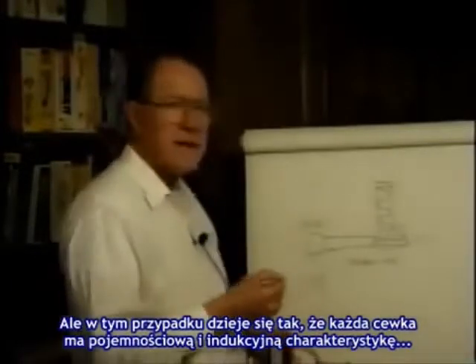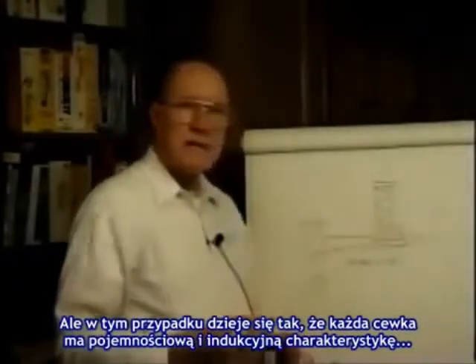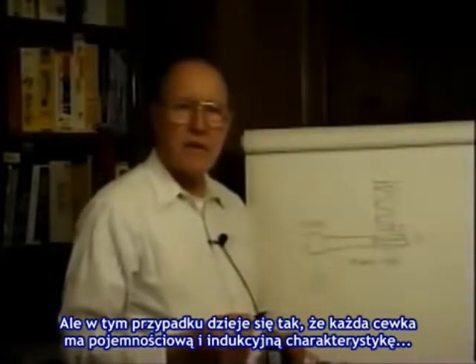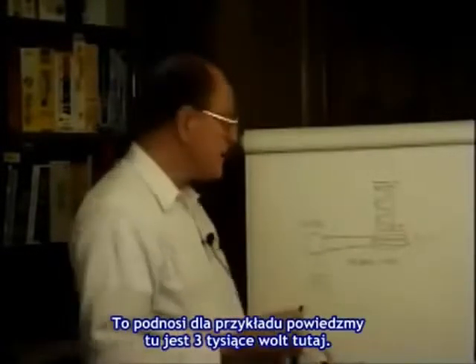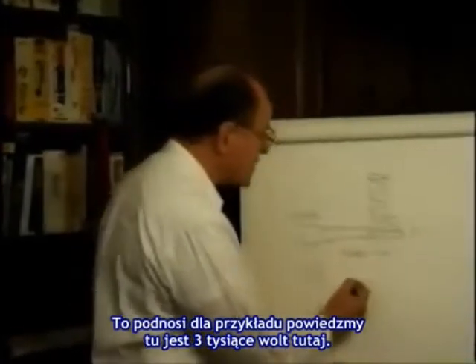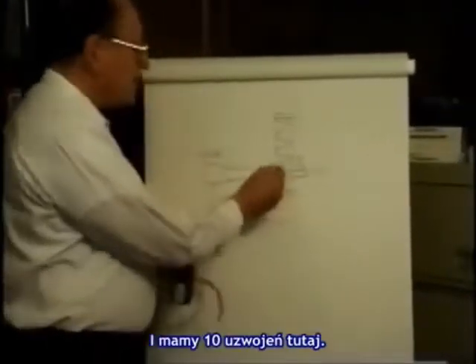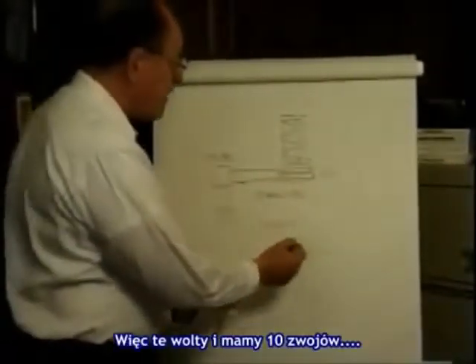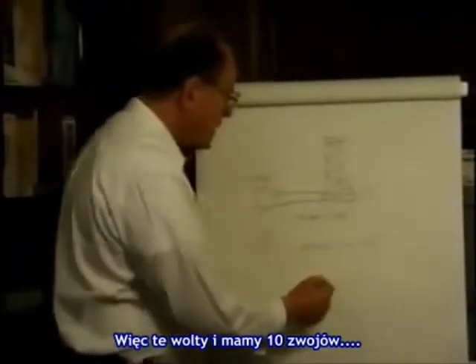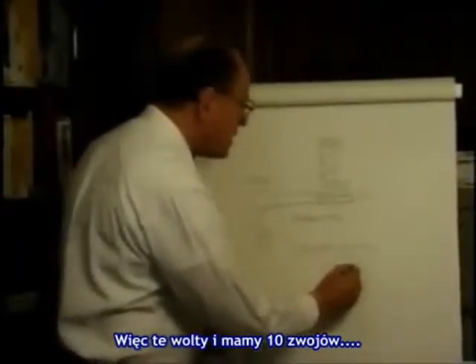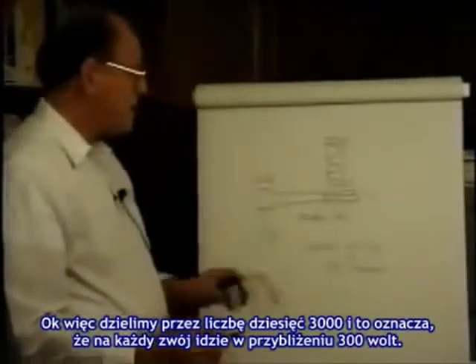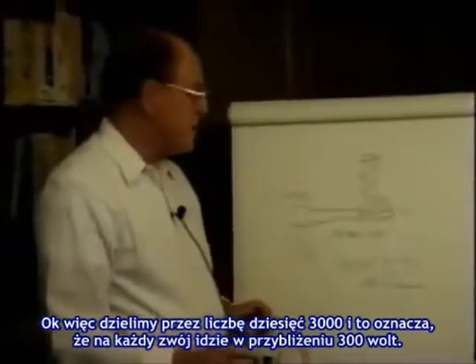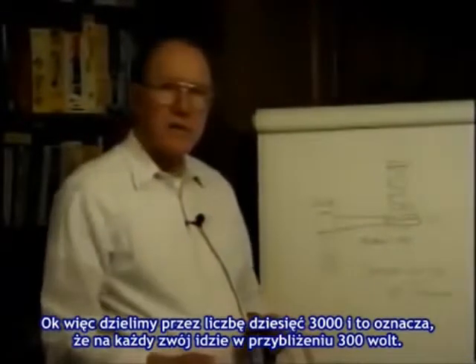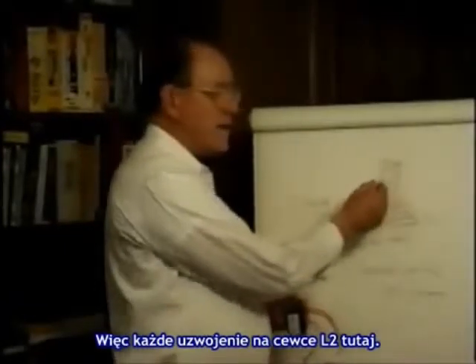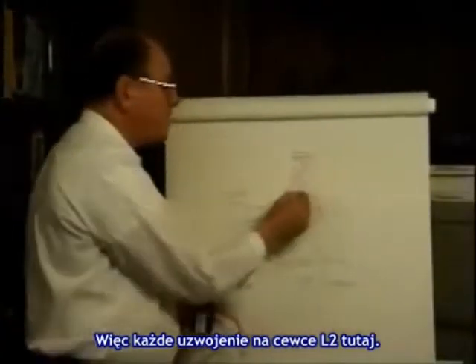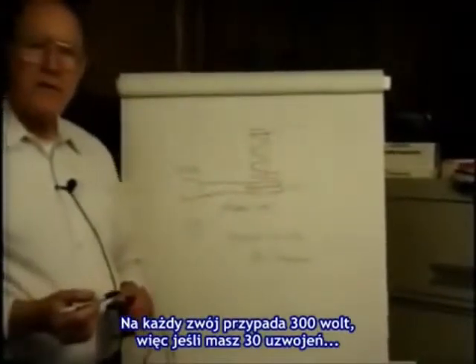But in this case, each coil has a capacitive and inductive characteristic, so it's magnifying. For example, say this is 3,000 volts here, and we have 10 turns. We divide 10 into 3,000, and that means each turn is going to equal 300 volts. So each turn on an L2 coil will have 300 volts on it.